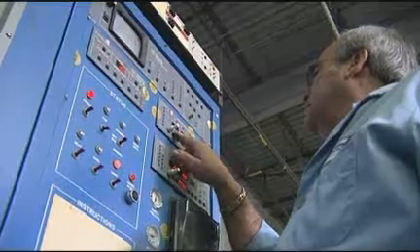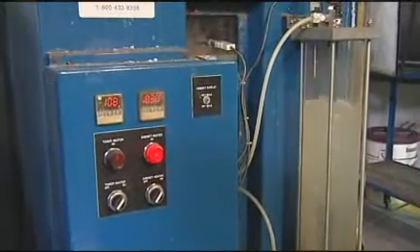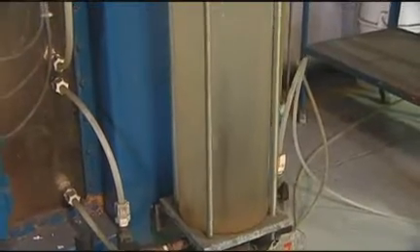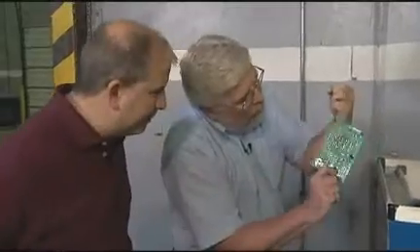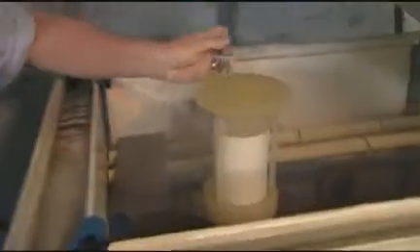In reliability, you do two types of tests: one designed to kill the component and find its weakest link, or one designed to age it rapidly to see failure rates as the product ages. Let's head out and take a look at the salt fog chamber. This is the salt fog chamber — it's a way of really driving a corrosion reaction. What you'll see is it's starting to develop some corrosion. What we're looking for is how good is the conformal coating on the board, how well the components are standing up, and whether we're getting ingress of salt fog under the relays. Every day we take the component out, rinse it with deionized water, dry it, and put it back in a unit to make sure it's still operating.